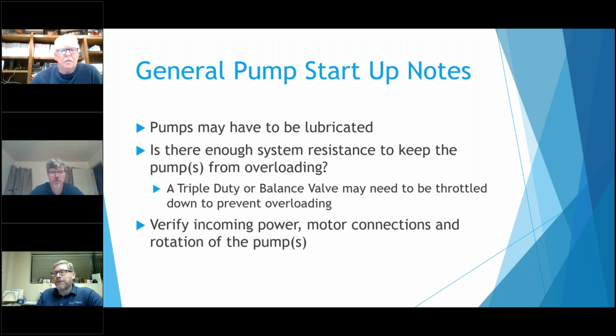The flow that it's going to put out is significantly less. So you're going to have a lot of flow issues, but it may actually pump, maybe if the pump is supposed to do say 300, it might actually put 25 or 30 GPM out there. You'll certainly have a lot of flow issues if it's running backwards, but it may actually provide the right pressure that you need.